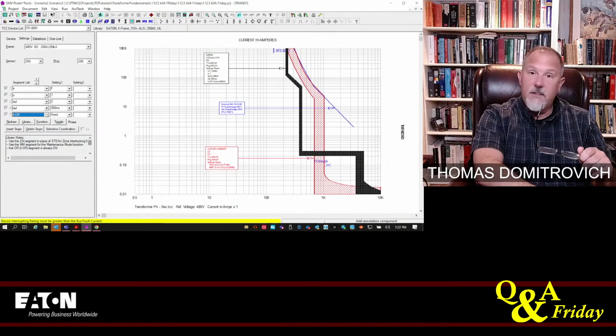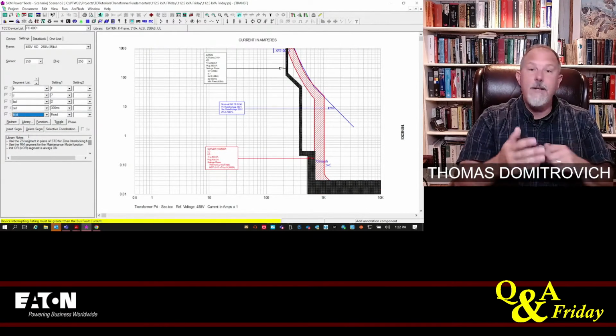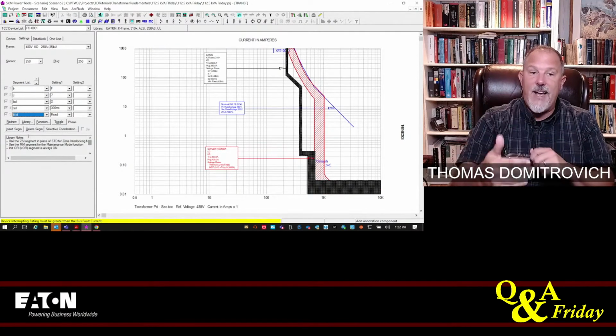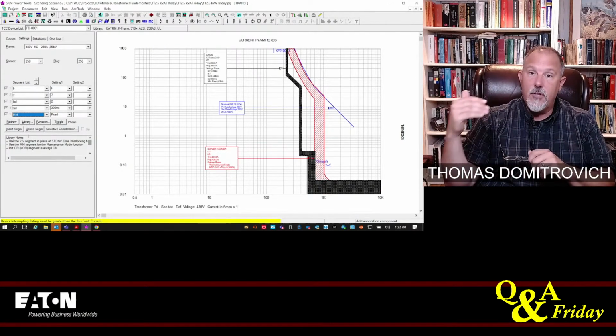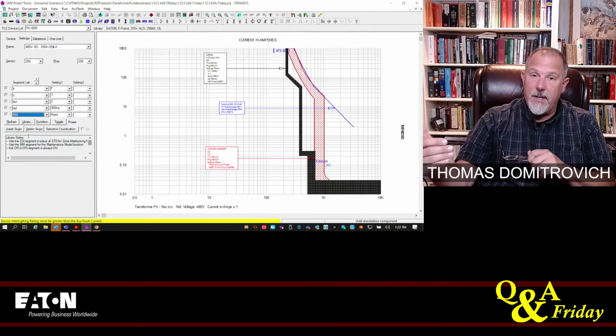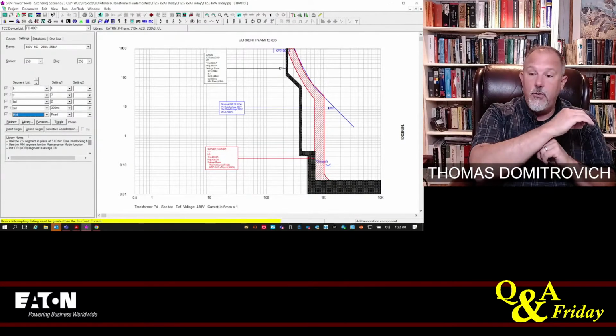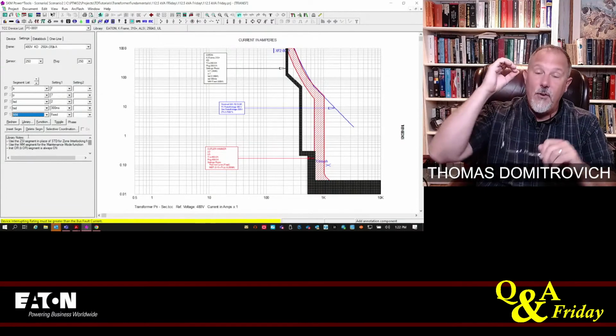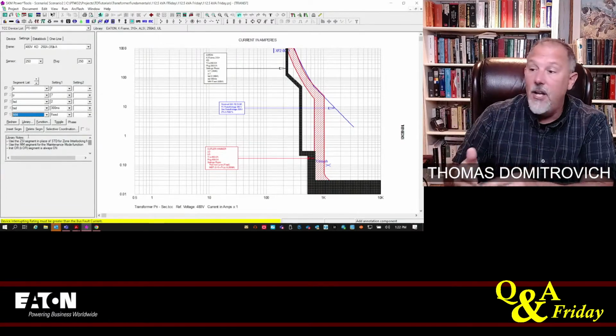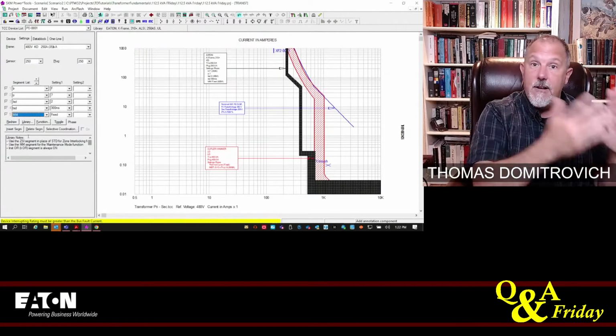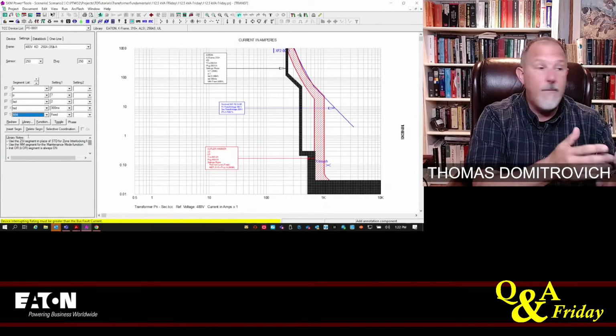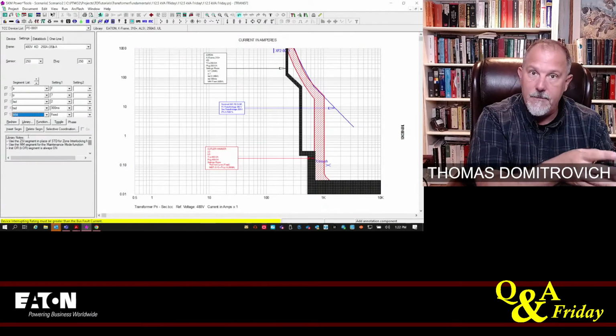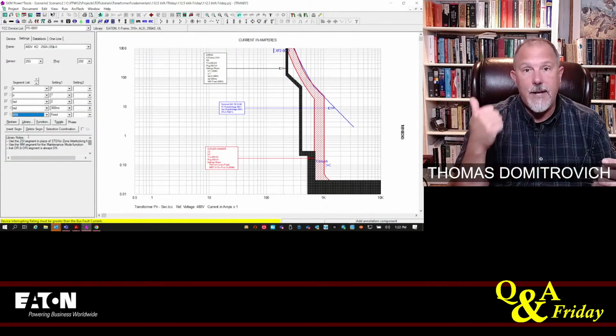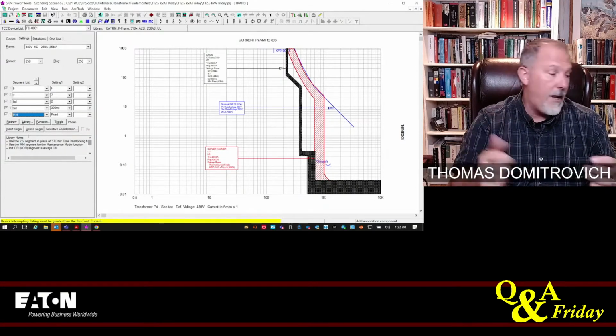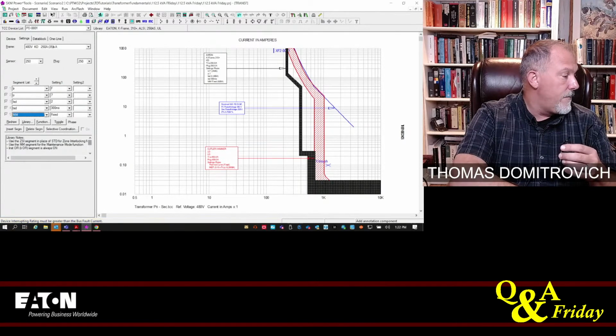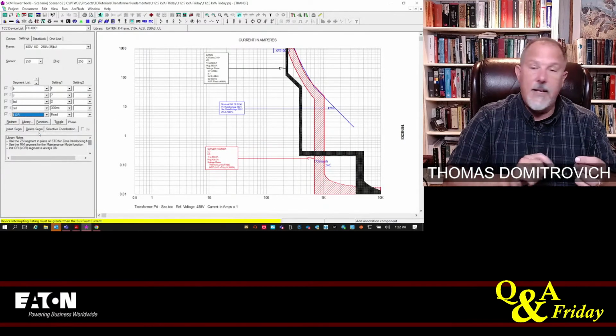You're going to do a justified energized work. You turn maintenance mode on. It changes the trip curve. It goes as fast as it can. If a fault occurs downstream, if you make a mistake, you lock and tag that out. You treat it just like you were going to, if you were going to establish an electrically safe work condition, you're going to follow the rules, which means you have to lock and tag out your overcurrent devices. You're going to do the same thing here. You're going to lock and tag that out in maintenance mode, go down, do your justified energized work, and then you come back and you put the instantaneous back in the picture.